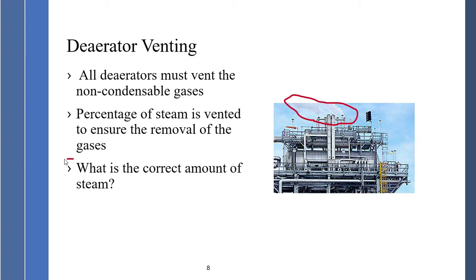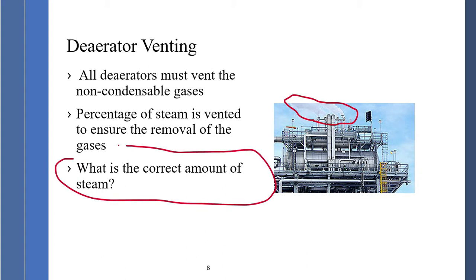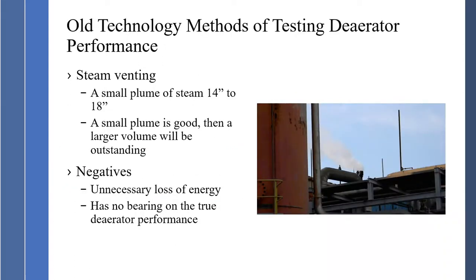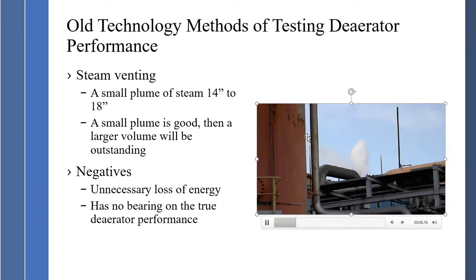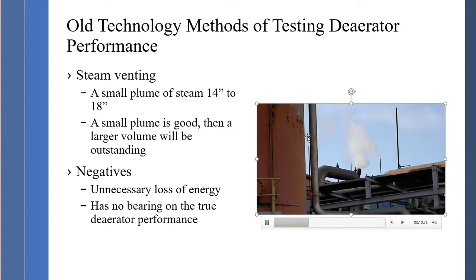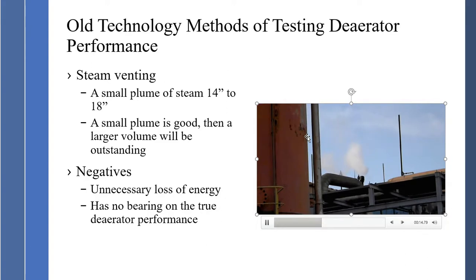The major question is: what is the correct amount of steam? How much steam should I be venting to ensure I am getting rid of the non-condensable gases? The old technology method of testing is steam venting — a small plume of steam, 14 to 18 inches. A small plume is good, a larger volume is outstanding, correct? Negative — it is an unnecessary loss of energy and has no bearing on true deaerator performance. It just says I am venting steam. You can see steam coming out of the deaerator operation here, but we don't know if this is the correct amount unless we measure dissolved oxygen.